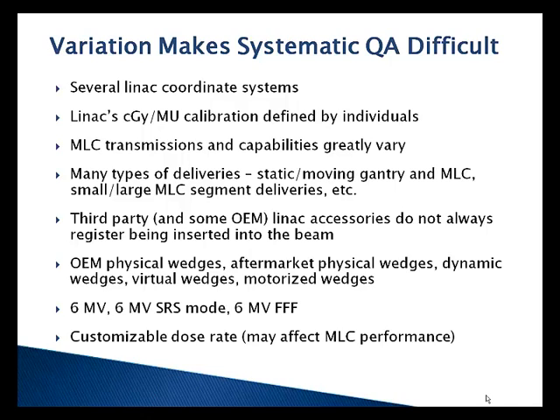Third party and even some OEM accessories like the SRS cone do not always register being inserted into the beam, so we can't always do an automatic check to make sure things are working correctly. Physical wedges, there's aftermarket physical wedges, dynamic wedges, virtual wedges, motorized wedges. There's so much complexity that we have to design for.